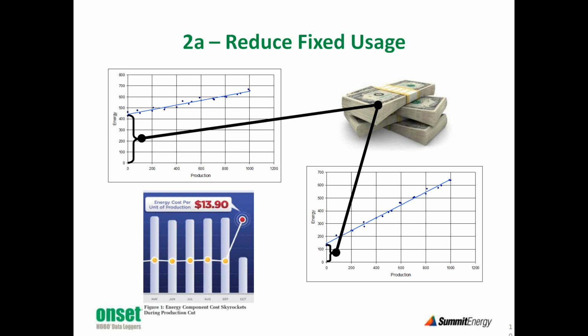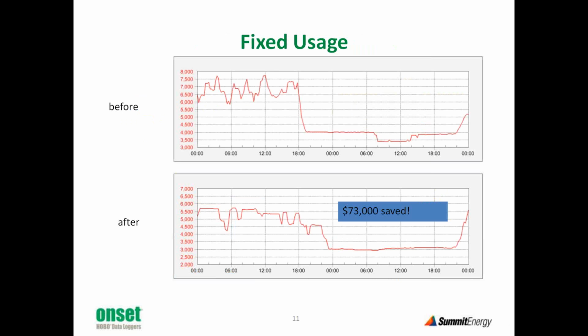So as you understand how large your fixed usage is and begin to understand what you need to do to reduce it, making measurements around the facility with the temporary recorders is what we do, helps to understand the components of that fixed usage. This is just an example from one of our clients that was just looking at daily load data. This happens to be for a Sunday from midnight to midnight, where the load during the day is 6.5 to 7 megawatts, 7,000 kilowatts on Saturday, and then on Sunday, which is the second day shown there, it levels out at about 4 megawatts.